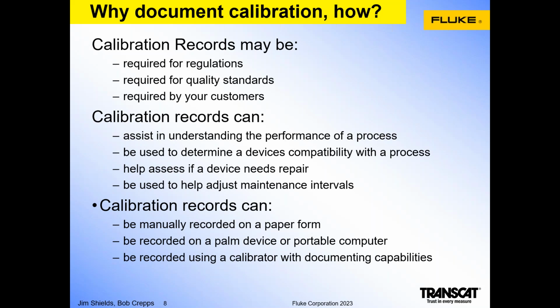And in the event that a device is always within calibration and has very little deviation or error, calibration records might be able to help and be used in adjusting maintenance intervals, wherein the interval could be extended to reduce maintenance costs. Calibration records can take a number of different forms. They can be manually recorded on a paper form with a clipboard in the field. They can be recorded on a tablet or portable computer in the field, and they can be recorded using a calibrator with documenting capabilities. And all three of these forms of documentation are all actively used in the field today.